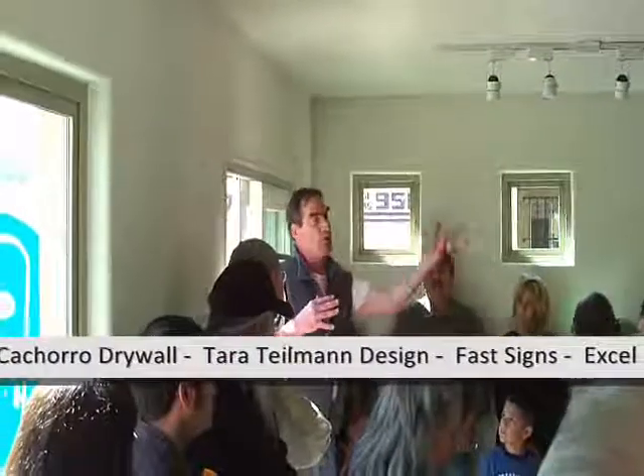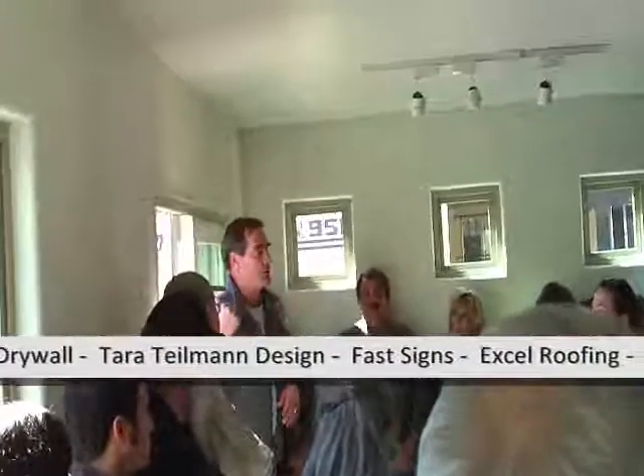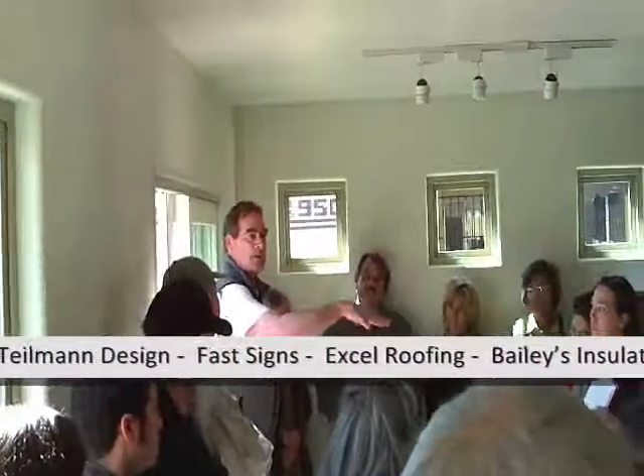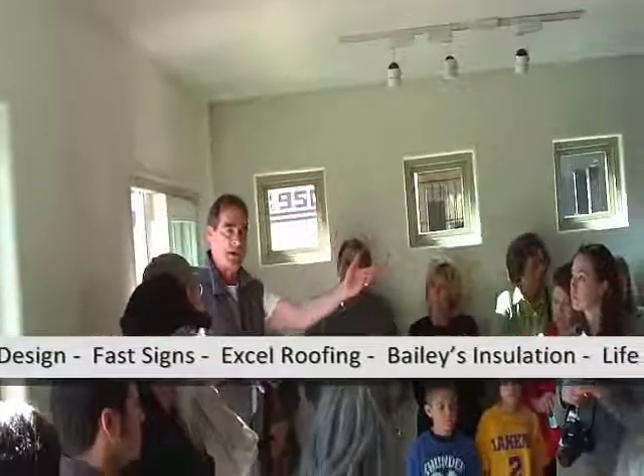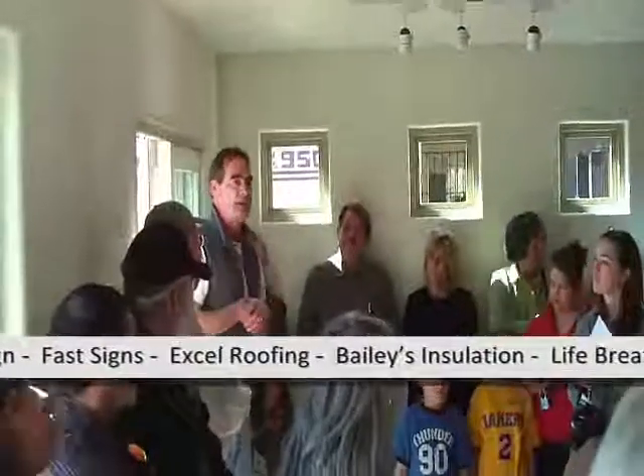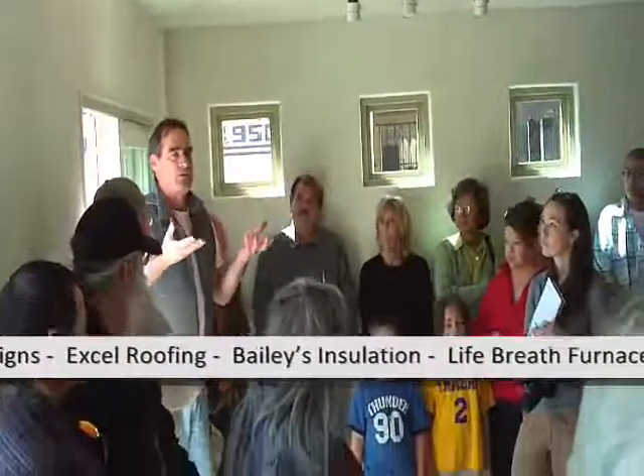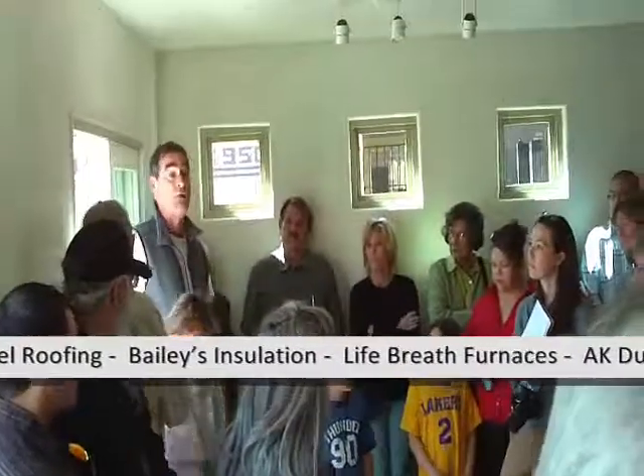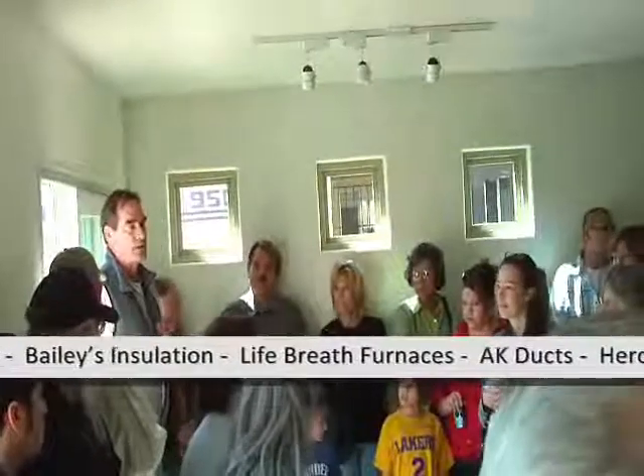means that fresh air will be coming into this house 24/7, and stale air will be exhausted 24/7. But the heat recovery ventilator passes the 72-degree stale air by the fresh air coming in. So if it's 0 degrees outside, it's bypassing that 72-degree air, and it actually takes heat out of the 72. So when it goes into the forced air system, it's more efficient.